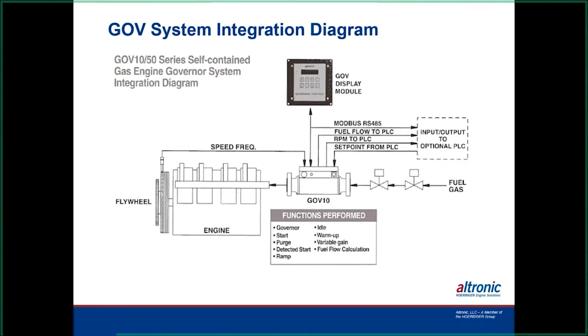This just gives you the layout of the valve. You need a speed pickup on the flywheel to bring that in. And then, of course, you need the 24 volts. Because it's being powered by the gas itself, it doesn't require very much amperage. It's only around 2 amps it operates on.